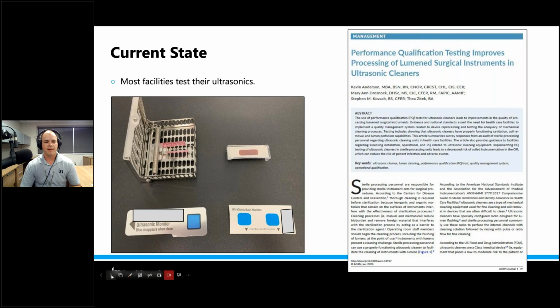But as you can see on the left here, I indicate here most facilities are testing their ultrasonic cleaners. All right, and that is a very good thing. However, in our experience and going around and collecting data on these ultrasonic cleaners and what people are doing in practice and in the field there, what we see most of the time is that one of these types of cleaning verification type products are being used. Okay, and understand that all of these products are soil removal tests. Okay, they're not testing for cavitation specifically, and they're not testing for soil removal within lumens.